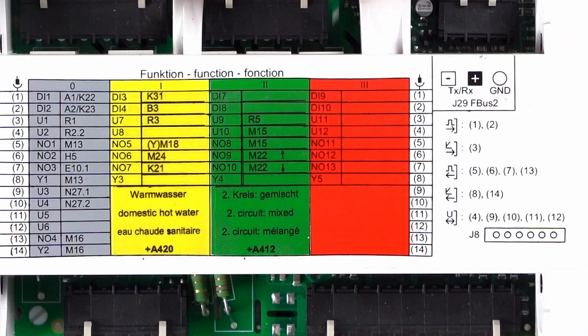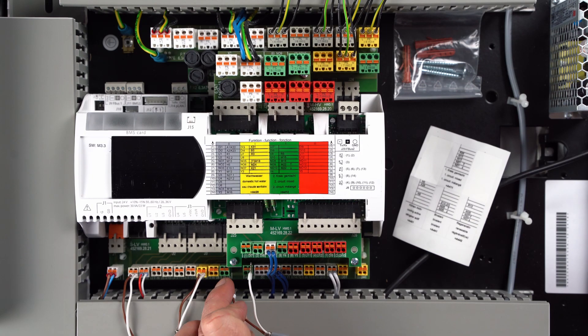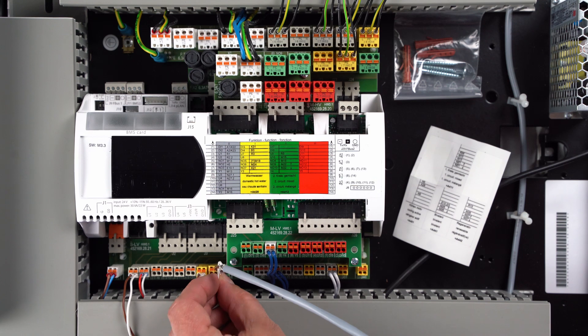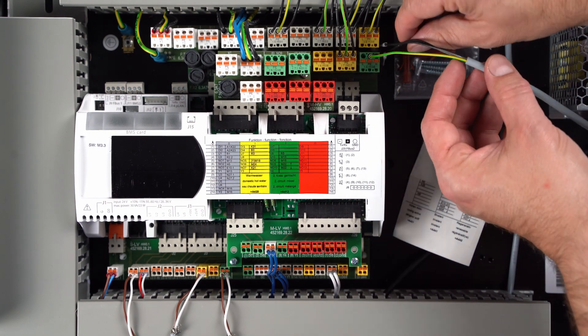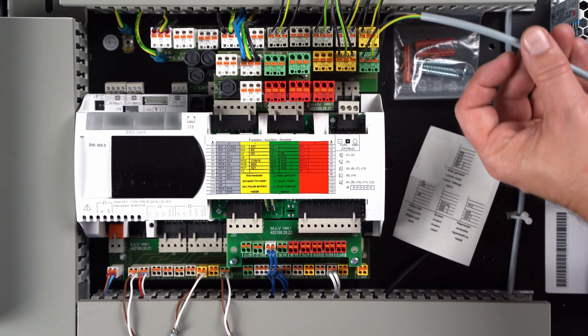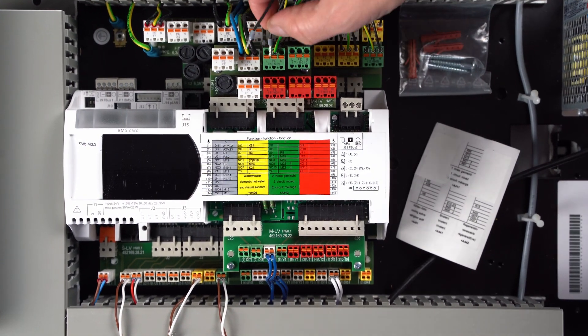The respective inputs and outputs on the green function block are described and assigned on the quick installation guide supplied. The sensor R5 is clamped to the green connector 3, U9. The circulation pump M15 is plugged into the green plug 5, NO8. The mixer M22 is clamped onto the green plugs 6 and 7, NO9 and NO10.